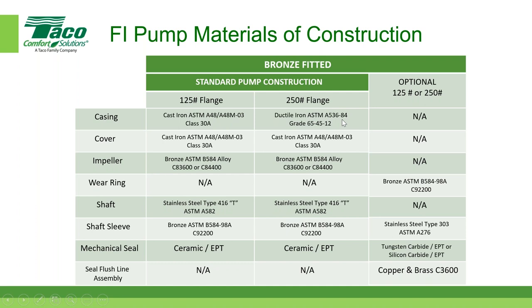Okay, the casing itself, but notice the covers for both are the same. So our engineers, when they did their design work, were able to use the same covers. As a manufacturer, you try to limit as much inventory and shelf numbers as you can, and that's what we were able to do there. And then you can see the impellers for the most part are bronze. We don't have a wear ring as a standard. You can order one as an option. Some folks have that in their spec, so our reps do order them as an option there.